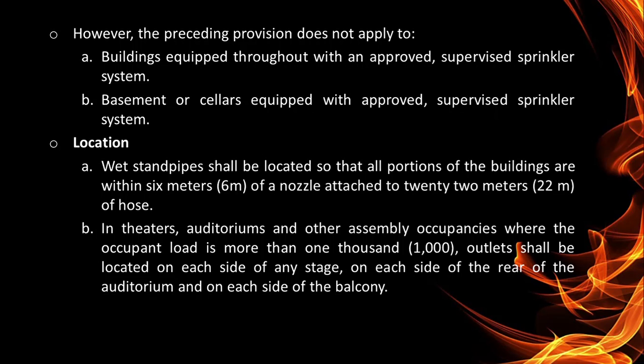However, the preceding provision does not apply to buildings equipped throughout with an approved supervised sprinkler system, or basements or cellars equipped with an approved supervised sprinkler system. Location. Wet standpipes shall be located so that all portions of the building are within 6 meters of a nozzle attached to 22 meters of hose. In theaters, auditoriums, and other assembly occupancies where the occupant load is more than 1,000, outlets shall be located on each side of any stage, on each side of the rear of the auditorium, and on each side of the balcony.